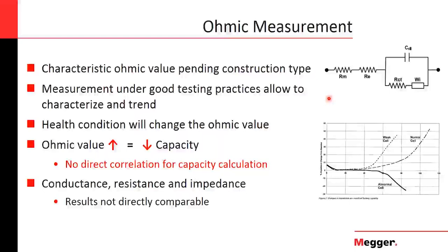As a general rule of thumb, when the ohmic value increases, when the resistance or the impedance increases, the capacity of the battery will be reduced. However, there's no direct correlation for capacity calculation, so you need to be careful when making conclusions, and you need to investigate further. There's 3 different methods to obtain this ohmic measurement. You can use conductance, you can use resistance, or you can use impedance. And one thing is that the results are not directly comparable.